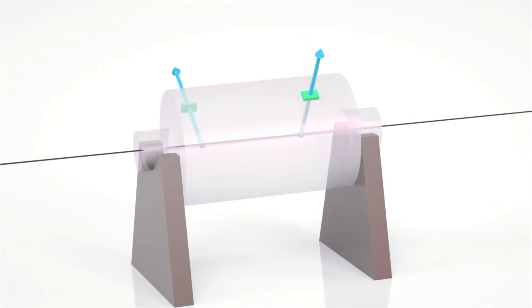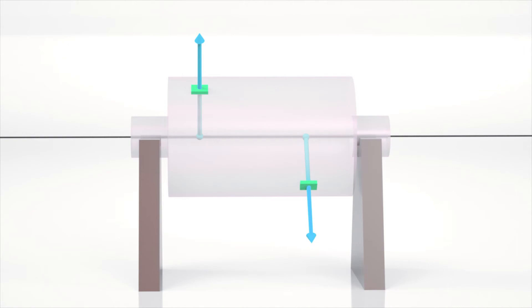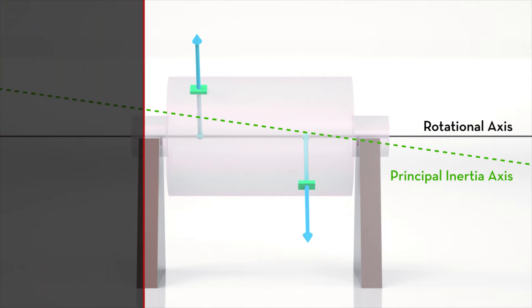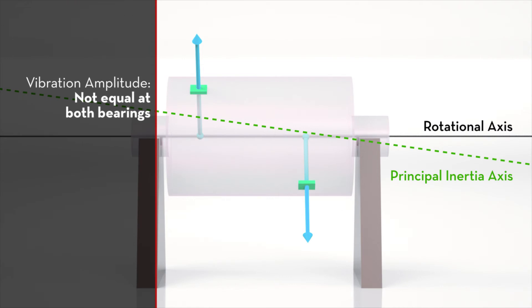Dynamic unbalance is a combination of static and couple unbalance. It occurs when the principal inertia axis is displaced from the rotational axis and does not intersect at the center of gravity. The two axes are not parallel. The vibration amplitude is not equal at both bearings. The phase angles are different.